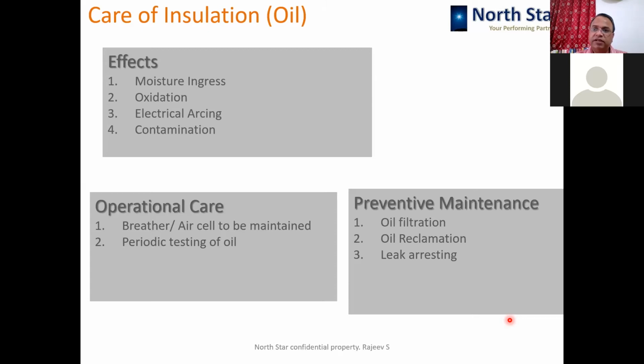So even though you are maintaining the breather very nicely, you ensure that the silica gel is blue in color, your air cell is in place, but if the transformer is leaking, then the moist air is going inside the transformer during cool off period, especially in the night and winter seasons. So leaks are not to be ignored and those are to be arrested as early as possible.